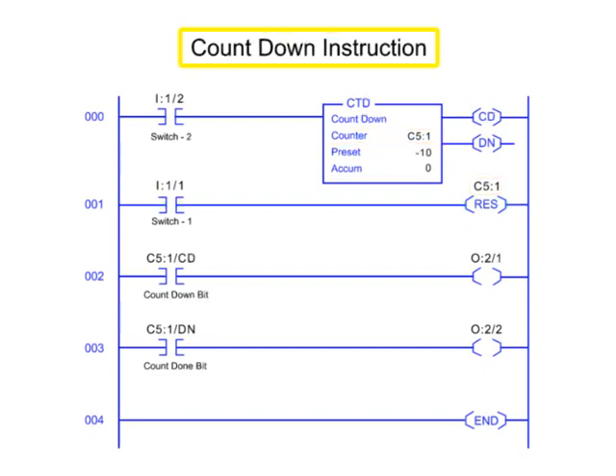The countdown instruction or CTD works the opposite way of the CTU by counting true to false rung transitions. When rung conditions for a CTD instruction have made a true to false transition, the countdown enable bit is energized and the accumulated value is decremented by one count.